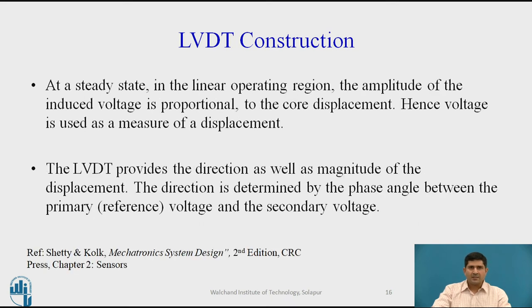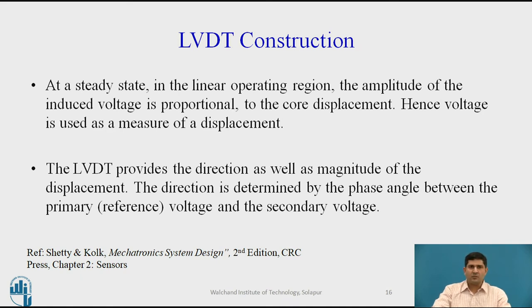At steady state in the linear operating region, the amplitude of the induced voltage is proportional to the core displacement, and hence voltage is used as the measure of displacement. The LVDT provides direction as well as magnitude of displacement. The direction is determined by the phase angle between the primary reference voltage and the secondary voltage. All sophisticated instruments will have additional signal conditioning circuitry to eliminate noise and account for non-linearities.